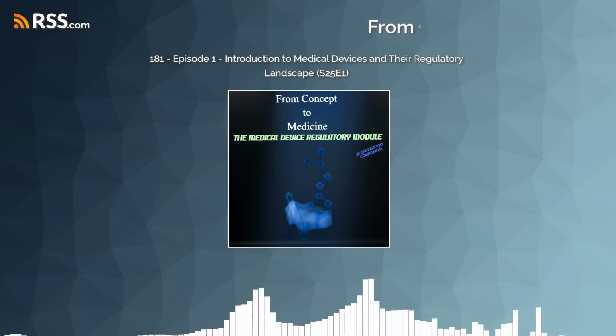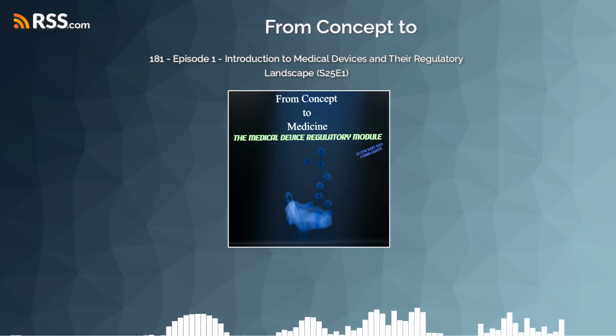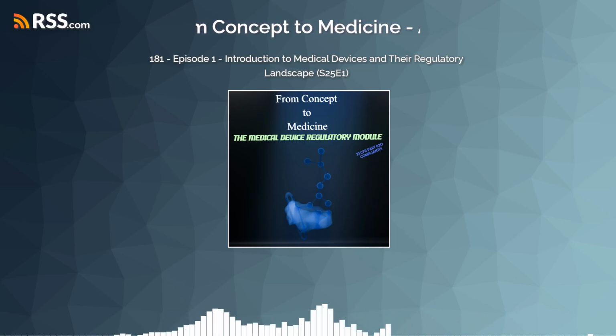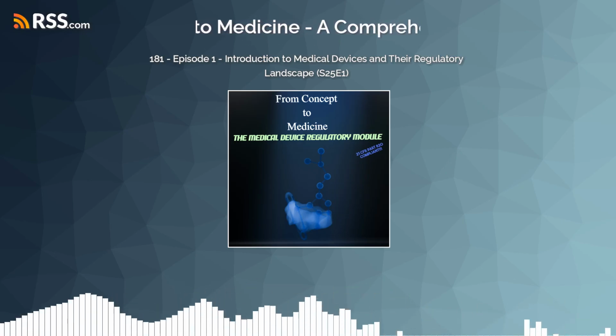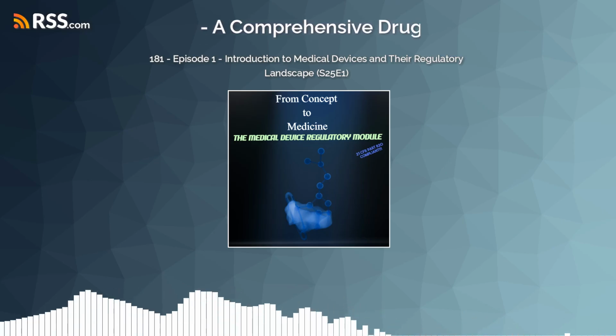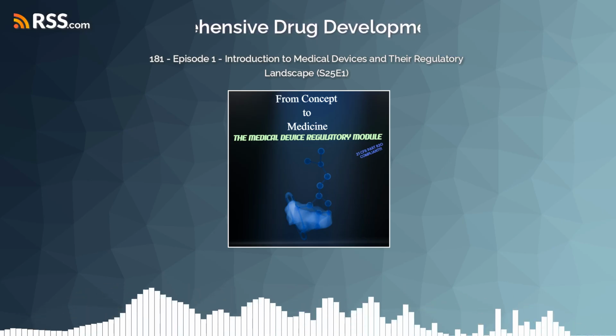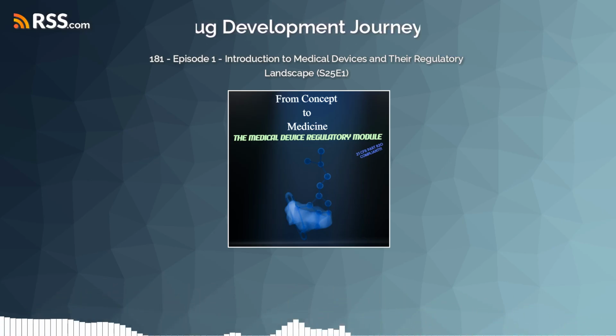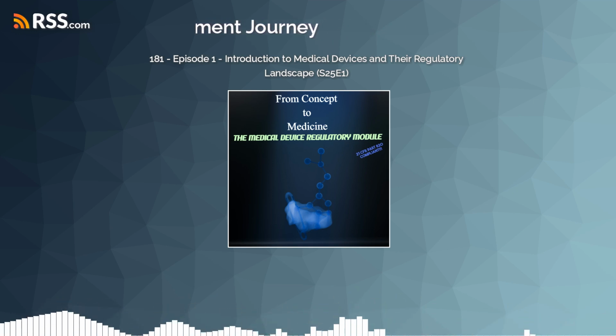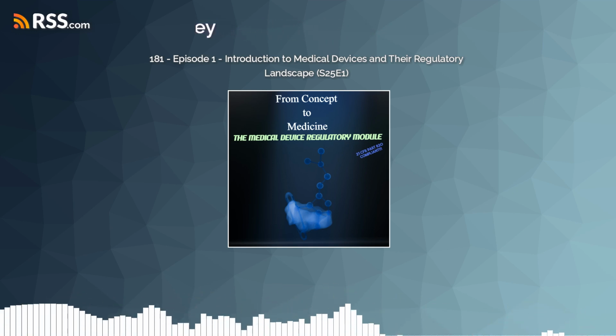Yes. For example, an elbow joint radial polymer prosthesis, so a partial elbow replacement, can fall into Class 2. Right. Now, what happens if there's a truly novel device, something moderate risk, but there's just nothing like it already on the market? No predicate for that 510K comparison. How does the FDA handle that kind of innovation?